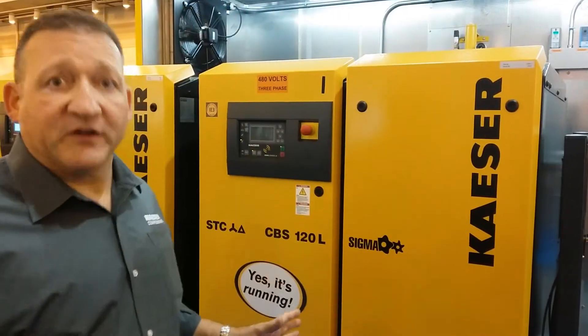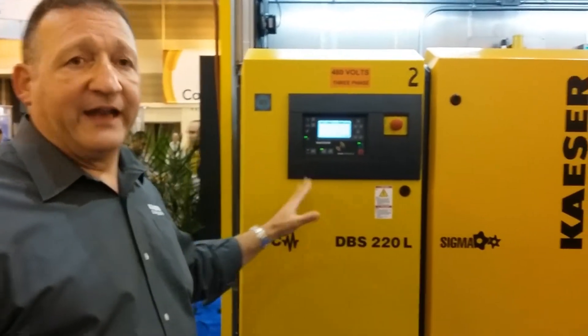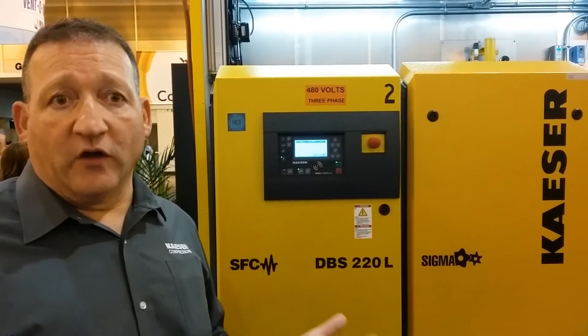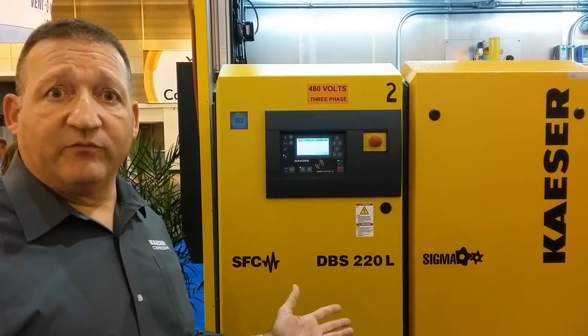The specific machines we have here are a variable frequency drive DBS rotary screw blower with a Sigma Control 2 controller. Every unit has its own IP address so you can connect to it via Ethernet or other buses and fully remotely monitor and control it. For example, you can connect this so that your DO dissolved oxygen sensor can provide a feedback loop to control the speed of a variable frequency drive blower, or turn blowers on and off as needed based on the flow requirement.